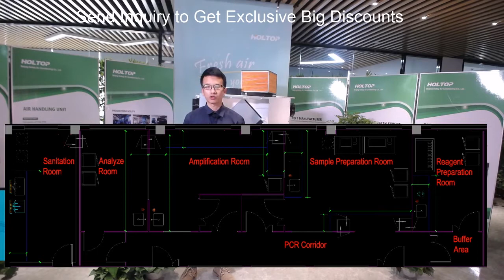Meanwhile, each room has its own airlock, and the room has a two-door interlocking system to guarantee air cleanliness and tightness. The test process flow is from the reagent room, reagent preparation room, to the sample preparation room, then to the amplification room, and finally to the analysis room. Only one way is allowed, which means a single direction.